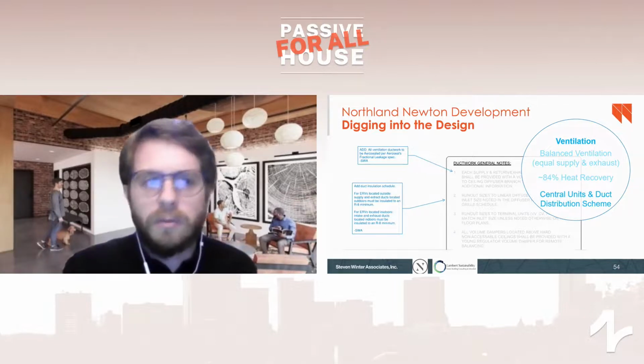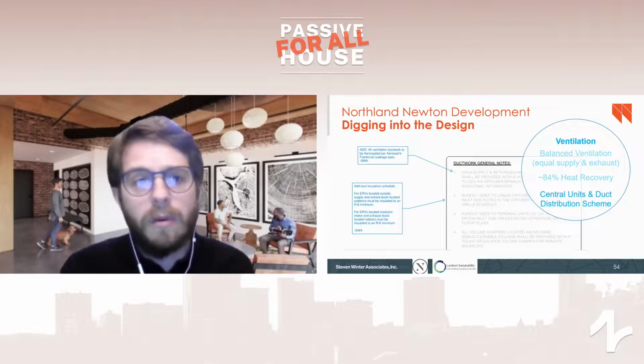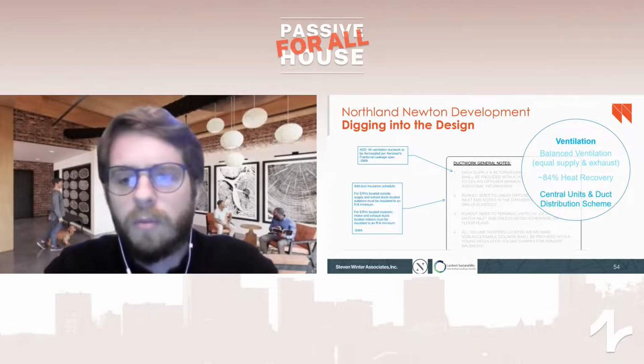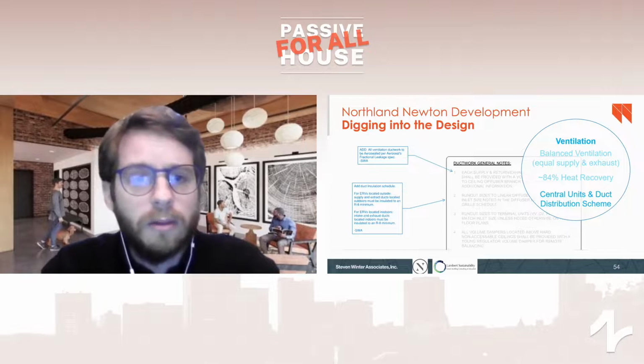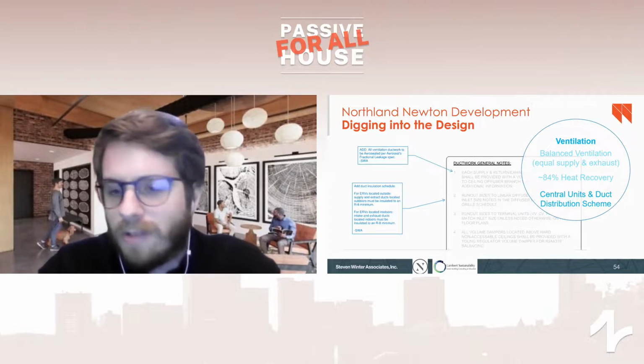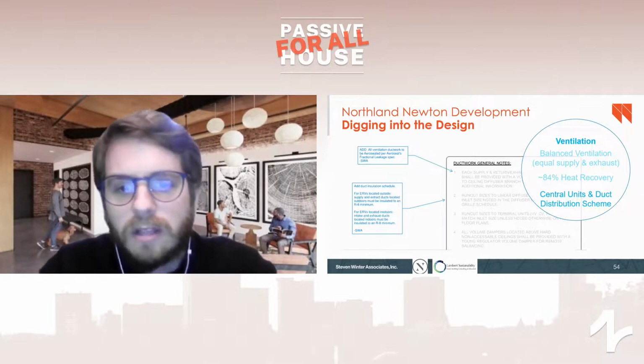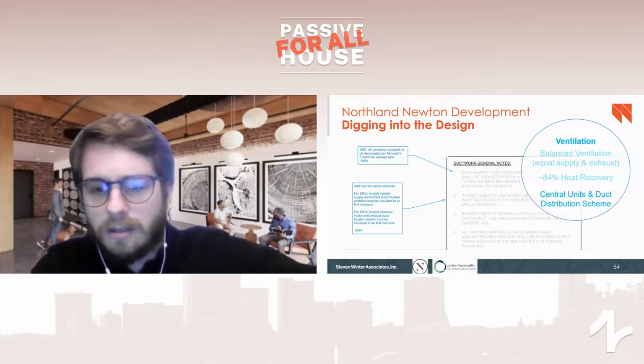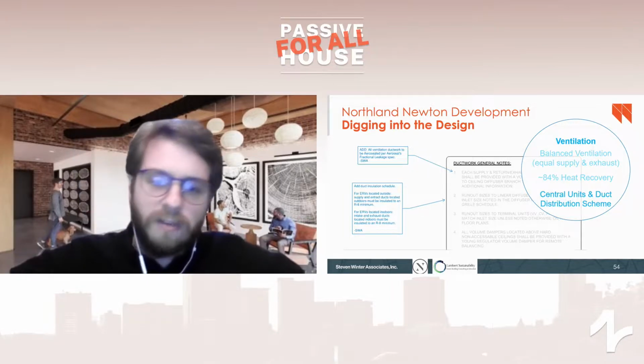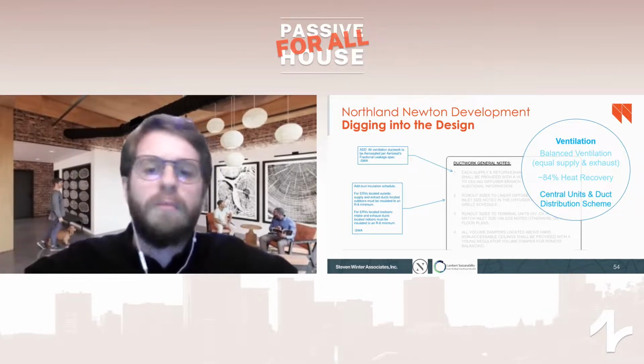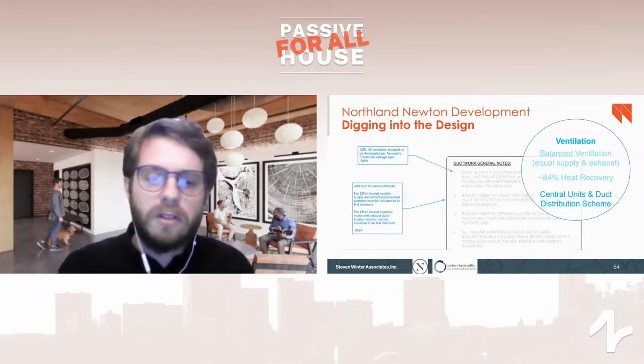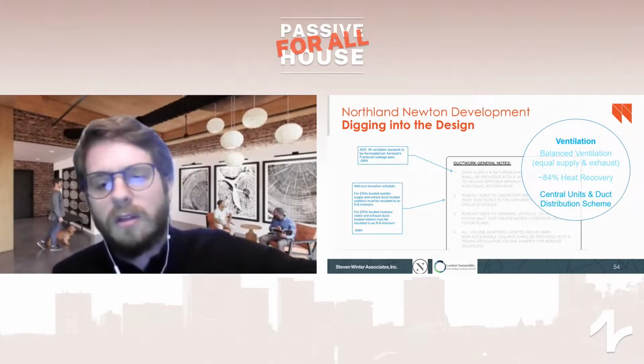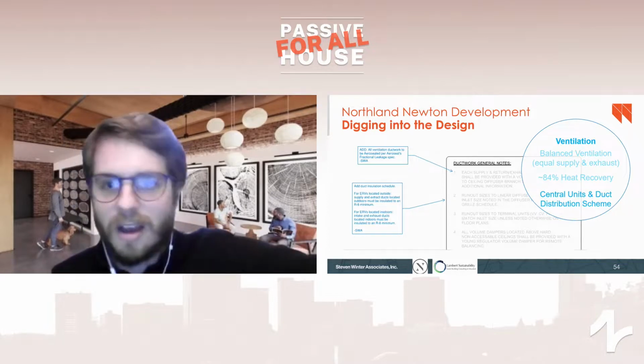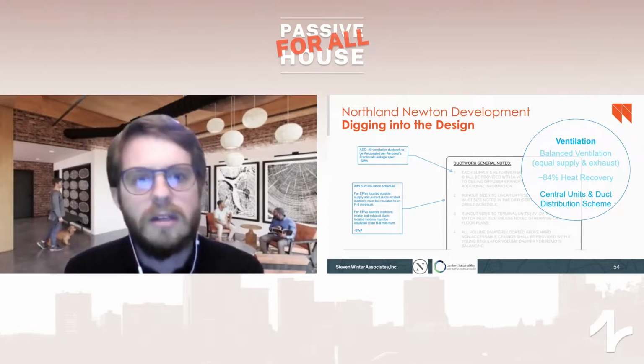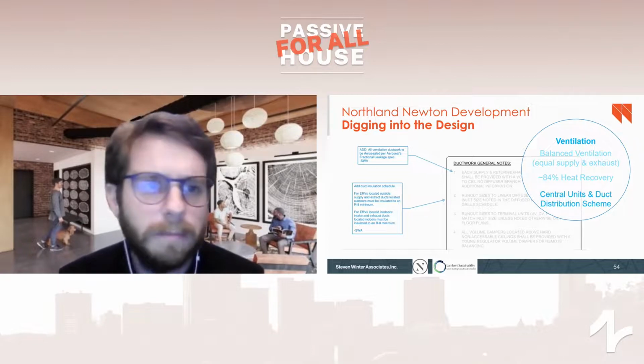So the aeroseal is really there to help ensure that the ducts are performing and not losing air, because any air that's lost from the ductwork system is air that's typically not getting to the desired register. And it's also additional fan horsepower that the ERVs have to make up for, and they have to eventually push more air through the building to get the air that we designed at the registers that is serving the building.